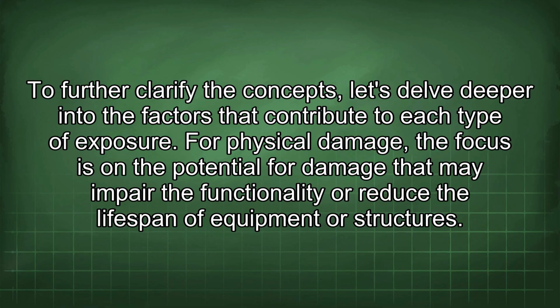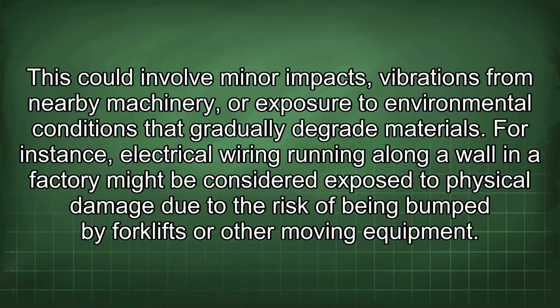For physical damage, the focus is on the potential for damage that may impair the functionality or reduce the lifespan of equipment or structures. This could involve minor impacts, vibrations from nearby machinery, or exposure to environmental conditions that gradually degrade materials. For instance, electrical wiring running along a wall in a factory might be considered exposed to physical damage due to the risk of being bumped by forklifts or other moving equipment.